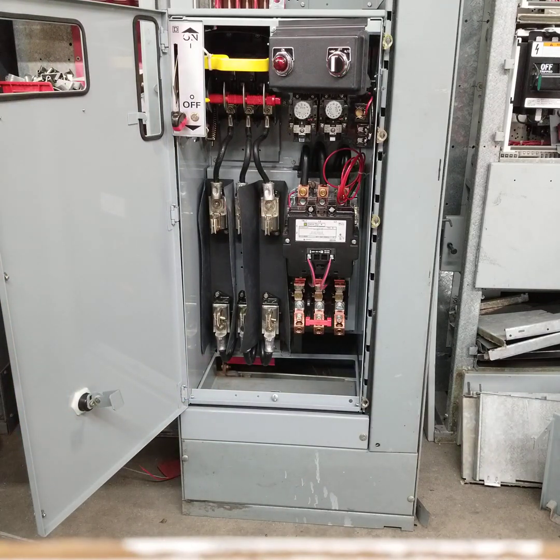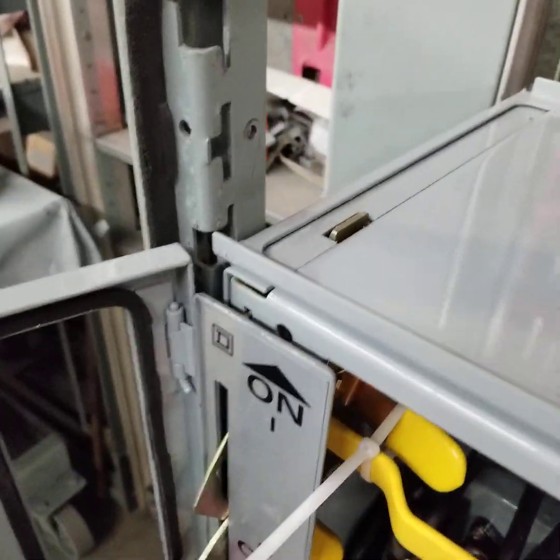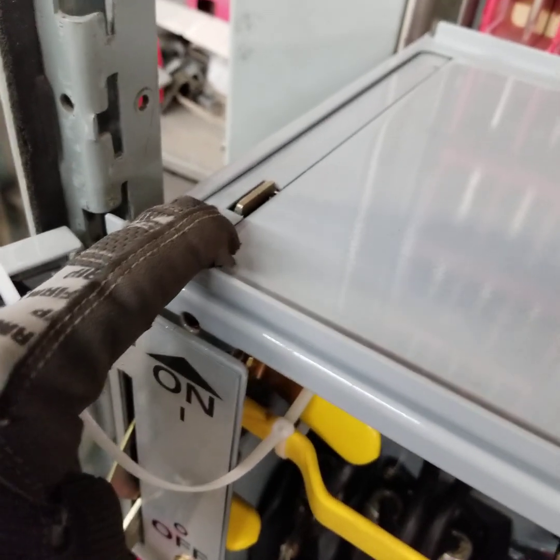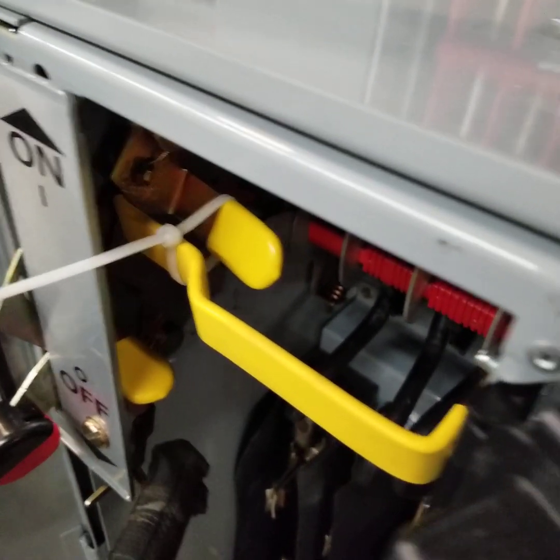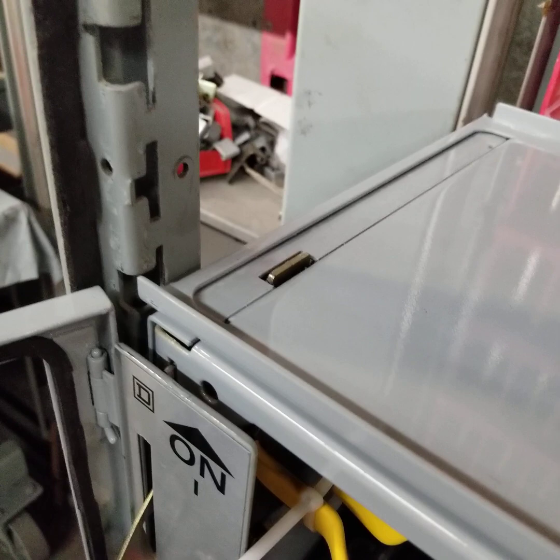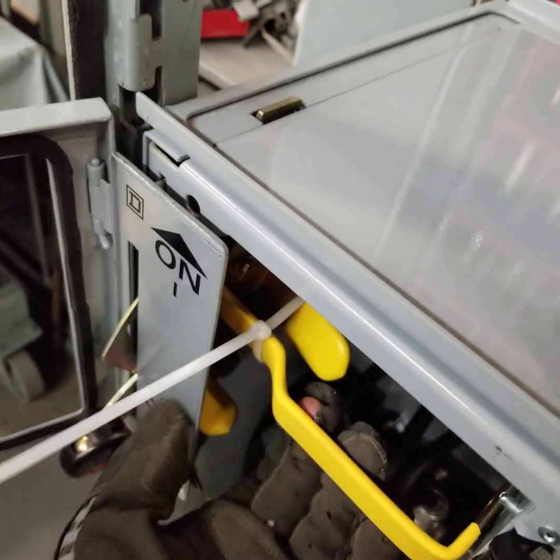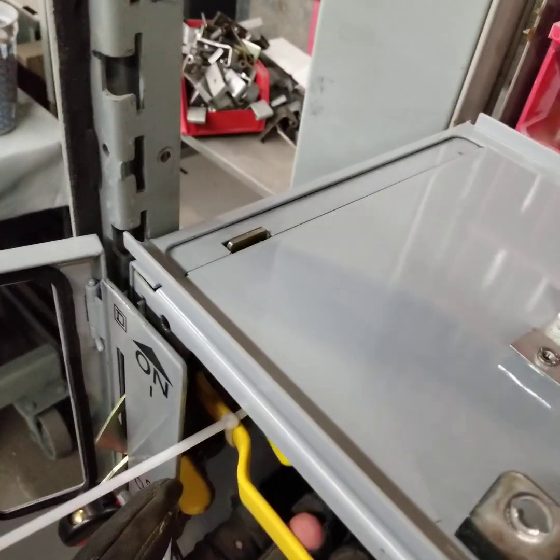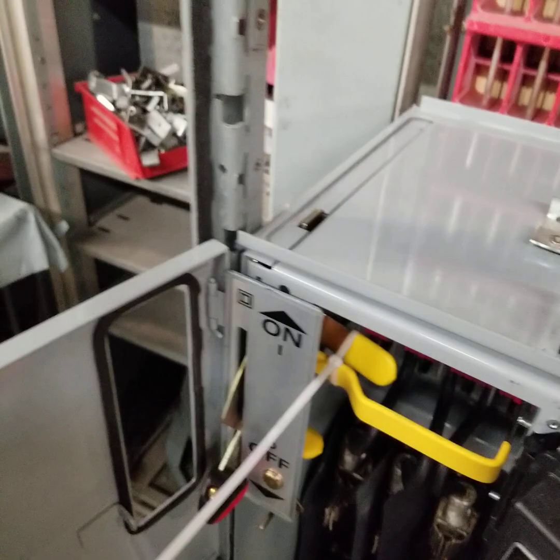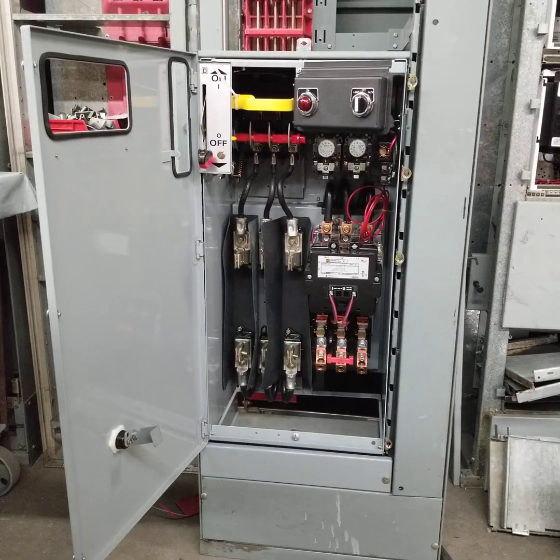We are now off the bus and have cleared the first interlock. However, in the next compartment, there is a piece of interlock holding onto the mid shelf — if that does not drop lower, we can't get the unit out. That drops by pressing on this particular yellow piece. If the switch is all the way back, you'll see it drop. The trick is holding the switch back with one hand while pressing the yellow piece with the other.